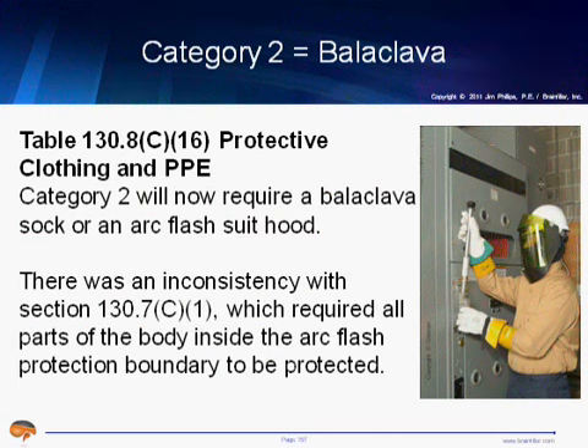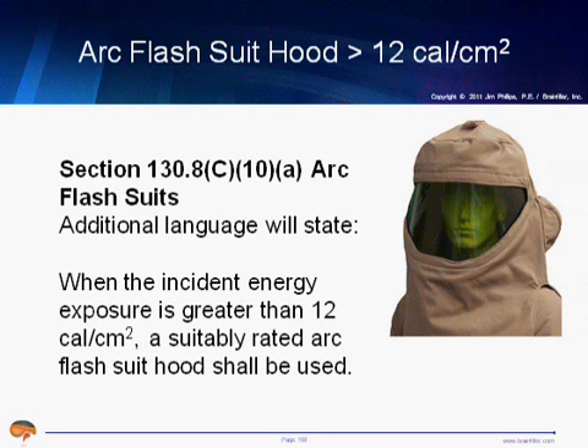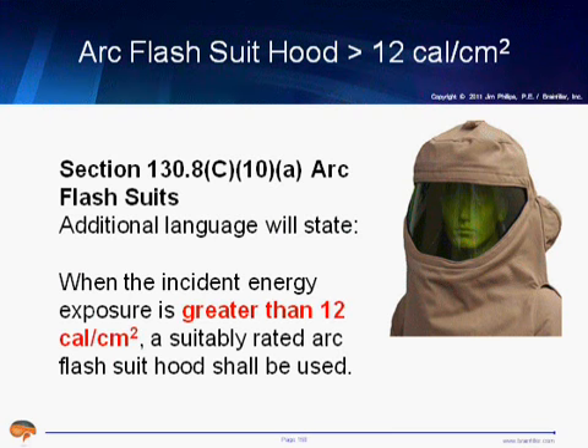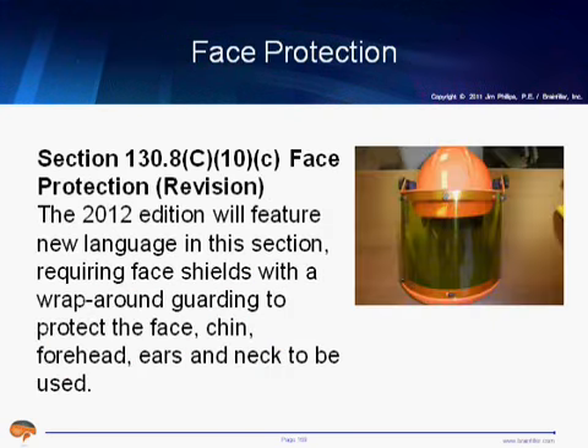Category 2 is now going to require the balaclava sock, basically protection for the back of the head, because there were other parts of the code of 70E that would say you need to protect all parts of the body in the arc flash protection boundary, but that didn't always happen. The case where you have a calculated incident energy, 12 calories, you're going to be required to wear an arc flash suit hood. So if you have energies greater than 12 calories, you have to wear the arc flash suit hood. That's a new requirement for 2012. And for face protection, the requirement's going to be enhanced, requiring face shields with a wraparound guarding to protect the face, the chin, the forehead, ears, neck, and that's going to be a requirement.